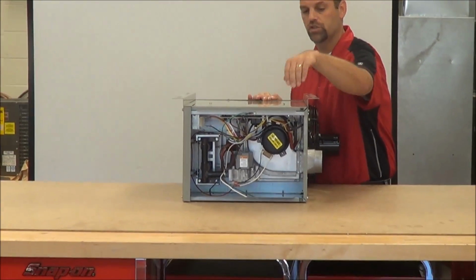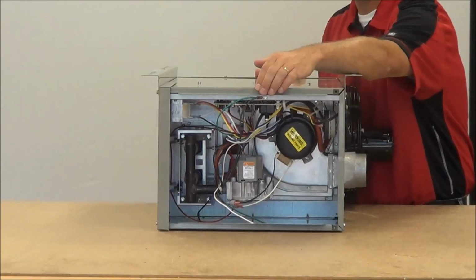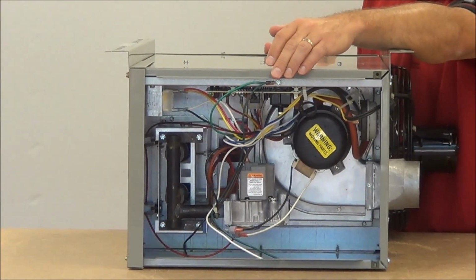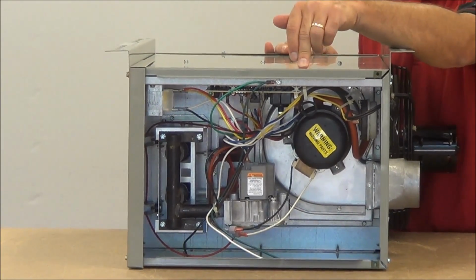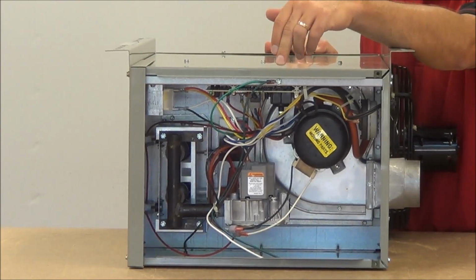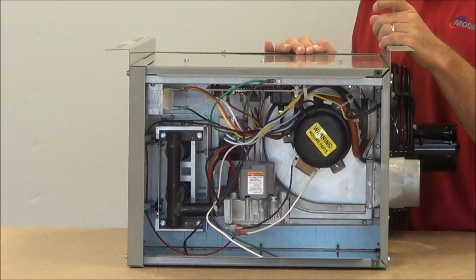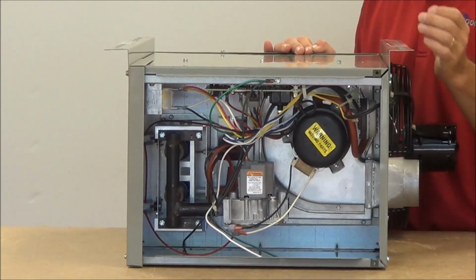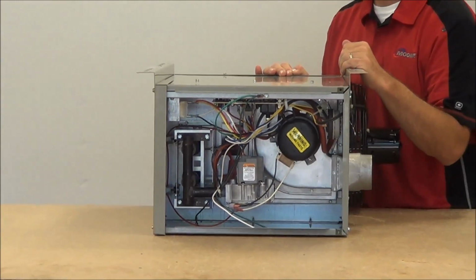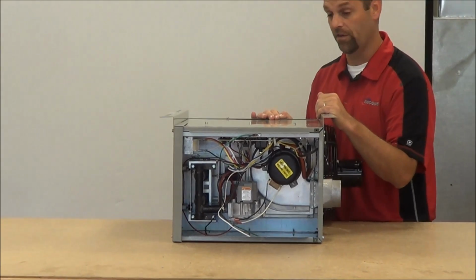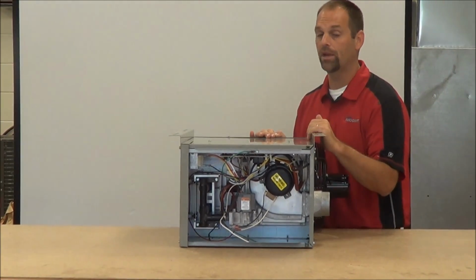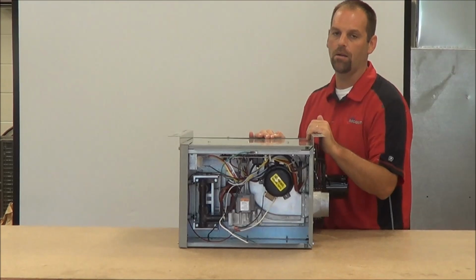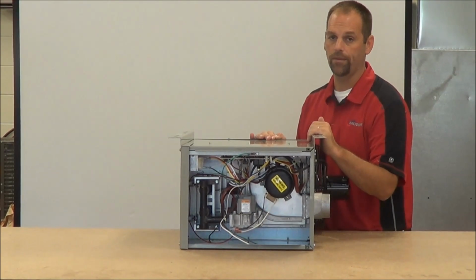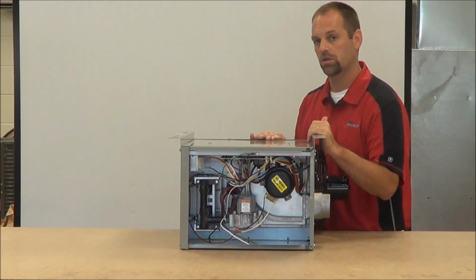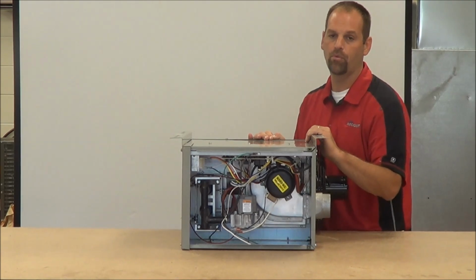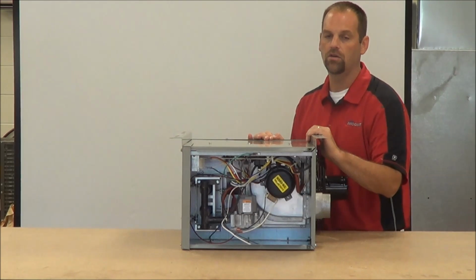At that point, I would make sure your power is shut off, and I would jumper out where your thermostat leads were. They should have gone to the terminals R and W on the control board. You place a temporary jumper in there, turn the unit on, and see if it functions properly. If it functions properly, and we're not blowing any more transformers, we've got a problem with the thermostat wire. It's more than likely a short if the lead length is right. At that point, you want to fix your wiring, and you'll be ready to go.